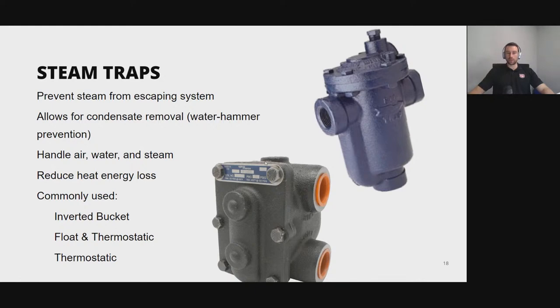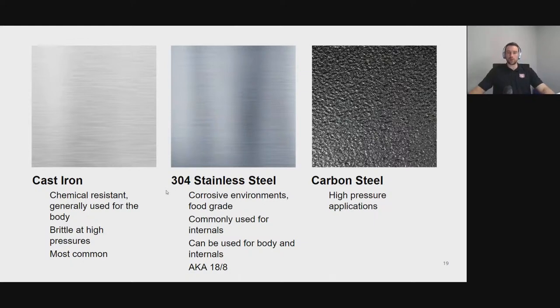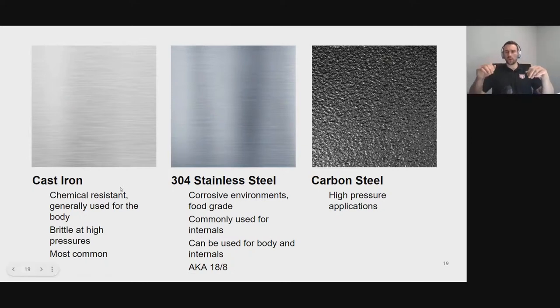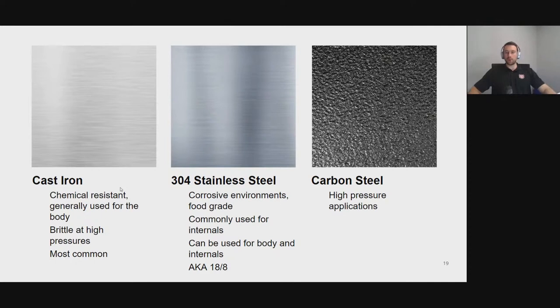The common types of steam traps are the float and thermostatic (F&T), the inverted bucket, and the thermostatic. Steam trap bodies are mainly going to be cast iron — it's cheap, chemically resistant, and fairly durable, but brittle at high pressure, so high-pressure applications may require carbon steel. The internals are probably going to be stainless steel to prevent corrosion over time. In a food-grade environment, you'd need stainless steel throughout to prevent corrosion from passing into food, though those traps are very expensive.